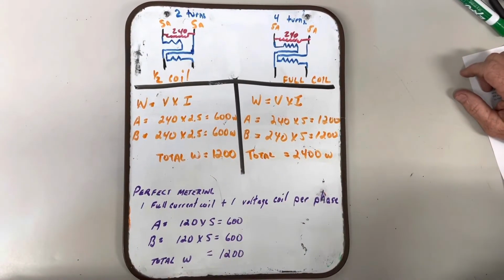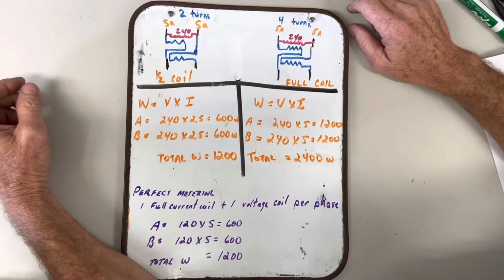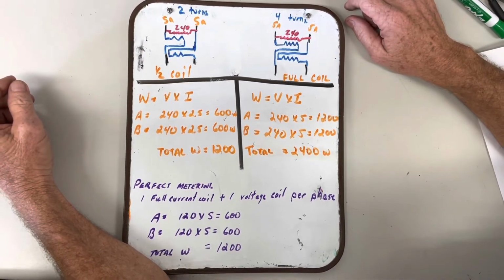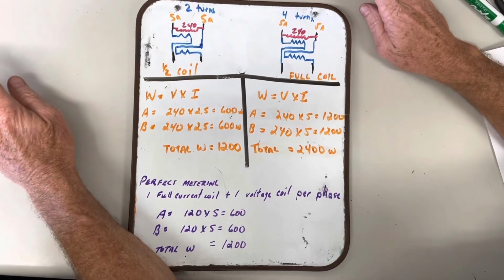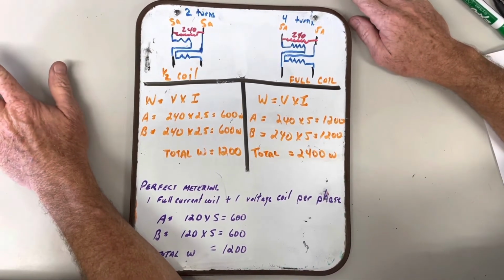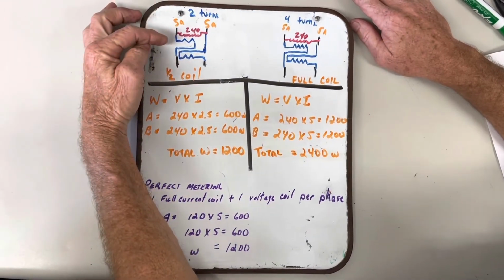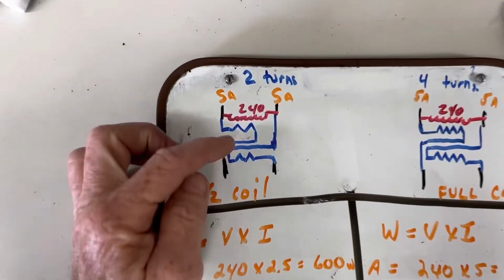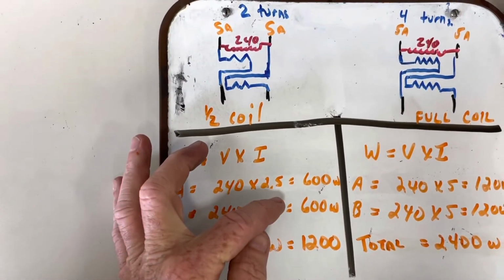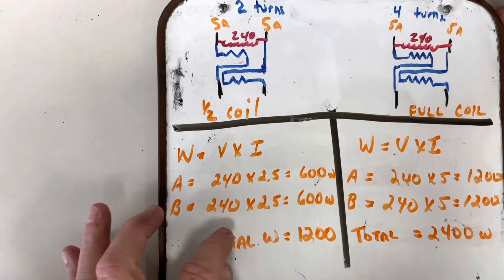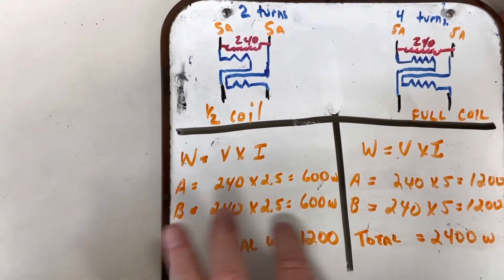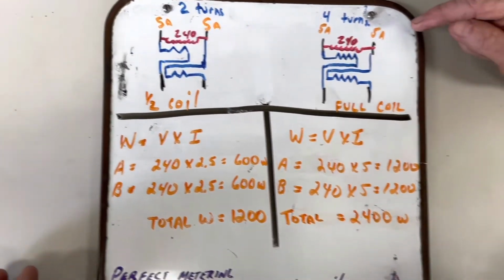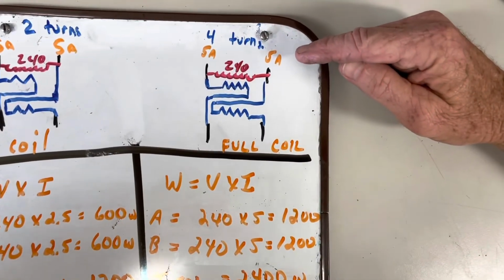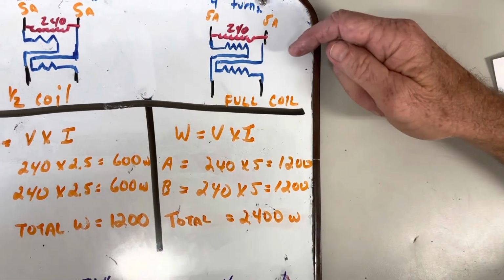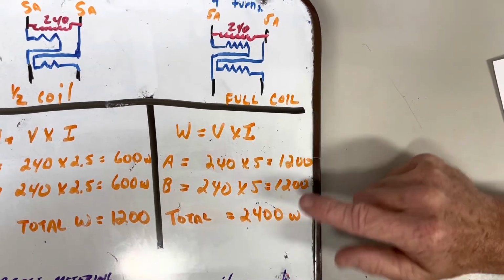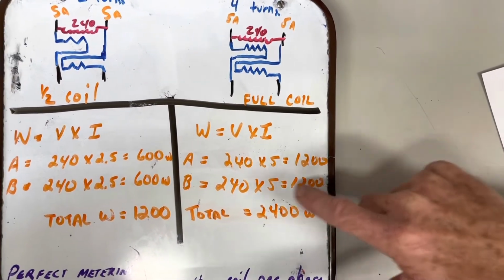Okay guys, this is going to be very difficult to explain, but in a Form 2S meter, we use half of a current coil instead of a full current coil. And I used some calculations to show exactly why this pans out this way. Okay, with half the turns, we can take the 240 volts times half the current will come out with a half a turn and get 600 watts on B phase and get 600 watts, we'll get a total of 1200 watts. Now if we use the full current coil, the formula would be 240, I'd get 5 amps out of each full coil. So 240 times 5 is 1200, I would get 2400 watts.